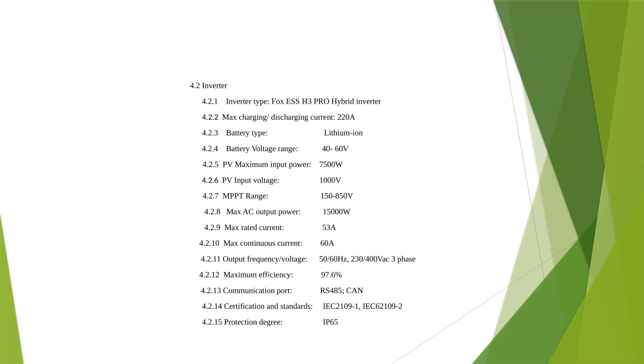Then our inverter type will be Fox ESS H3 Pro hybrid inverter with a maximum charging or discharging current of 220 amps. And the supported battery type for this inverter is lithium ion. And the battery voltage range should be 40 to 60 volts. And maximum input power to the inverter is 7,500 watts. And maximum PV input voltage 1000 volts, and MPPT range 150 to 850 volts, and maximum AC output power 15 kilowatt, maximum rated current 53 amps, and the maximum continuous current for this inverter is 60 amp.